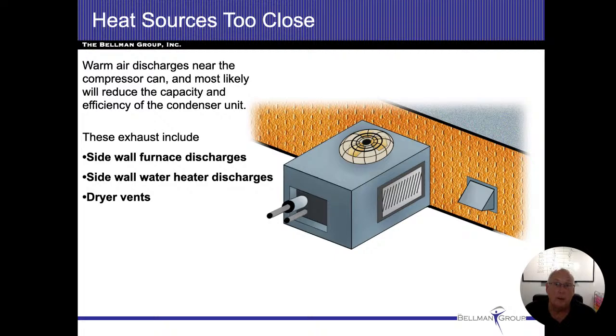However, the condensation that comes off of a sidewall vented furnace, because it is a condensing furnace, is very caustic. And if that gets blown onto the fins on a regular basis in the winter, we're going to start rotting and deteriorating those fins like there's no tomorrow, all right? So that in itself, I think, is a big deal. And yeah, the air shouldn't be blowing on the fins. It should be off to the side somewhere.